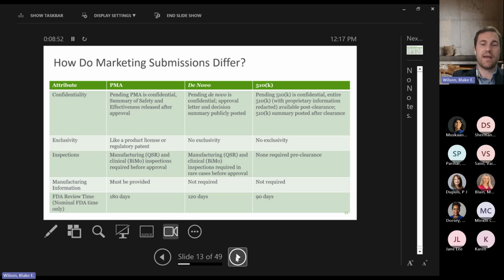As you can see with a 510K, FDA gets 90 days to review your application. With de novos, by statute, it's 120. FDA actually gets 150 under their MDUFA agreements with industry for user fees. And then for PMA, it's 180 days. Now, what I would note is that these are FDA review days that are associated with this. So if FDA stops the clock because they issued an additional information request to the company during the application process, those days don't count to the overall timeline.